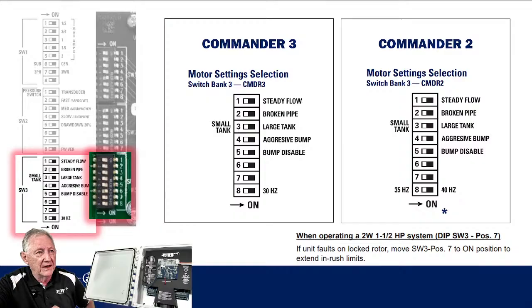But at any rate, these, down on the Commander 3 and the Commander 2, the third one down, if they've got a conventional pressure tank, I mentioned one of the reasons that these drives are popular is because you can upgrade an existing system. You can go from a 20-pound differential swing to a consistent pressure with a drive.